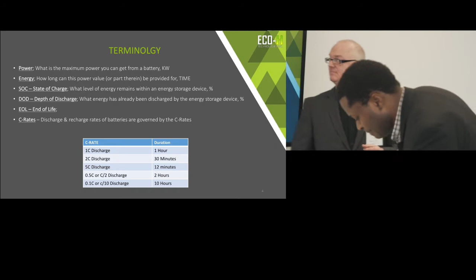SOC, state of charge - how much power is in the battery - is measured in percentage. So if you have a typical 9-volt battery that's fully charged, that's 100%. When you take out 50% of it, you've taken out 50%, so you're left with 50% depth of discharge. The way I remember this, there's a small d at the end of discharged, so it's what's discharged. So if a battery or energy storage system has a state of charge of 40%, then it's discharged 60%. So there's a relationship.